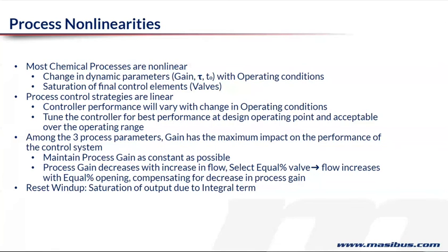Then there is also a phenomenon called reset wind up. I just explained that some control valves reach their maximum flow not at their 100% position. They may reach it at 60%, or sometimes a butterfly valve maybe even at 50%. Now what happens? Your PID controller is giving an output which is increasing, but the control valve cannot increase beyond some point, or even if it increases, it doesn't have an impact on the process.